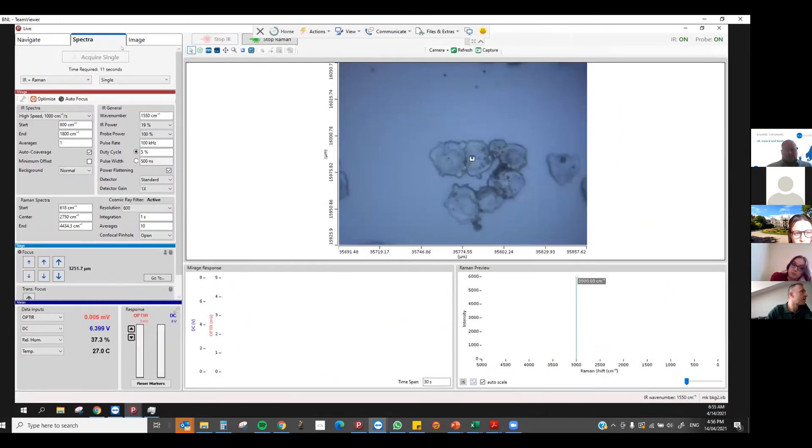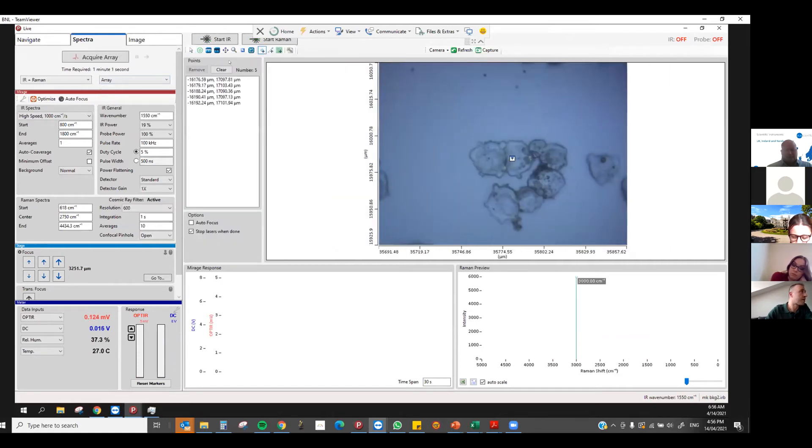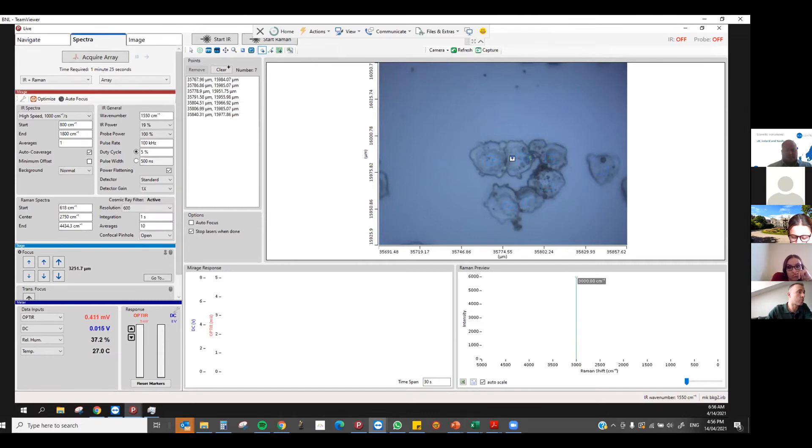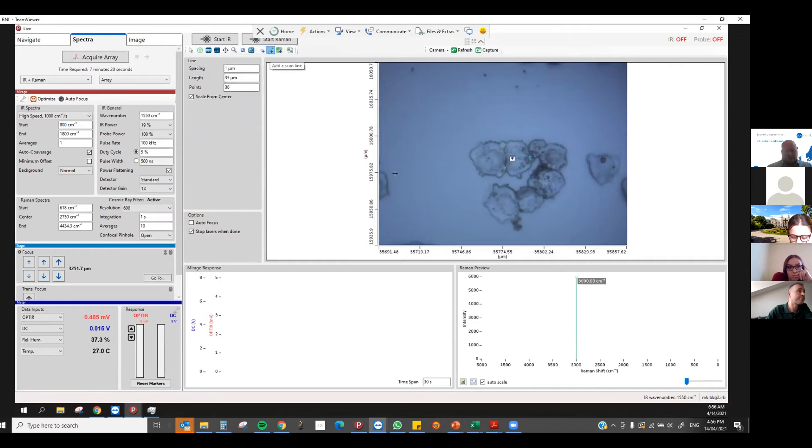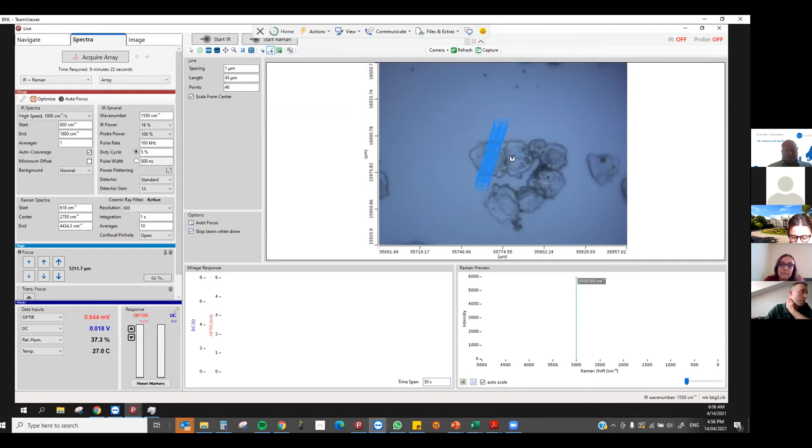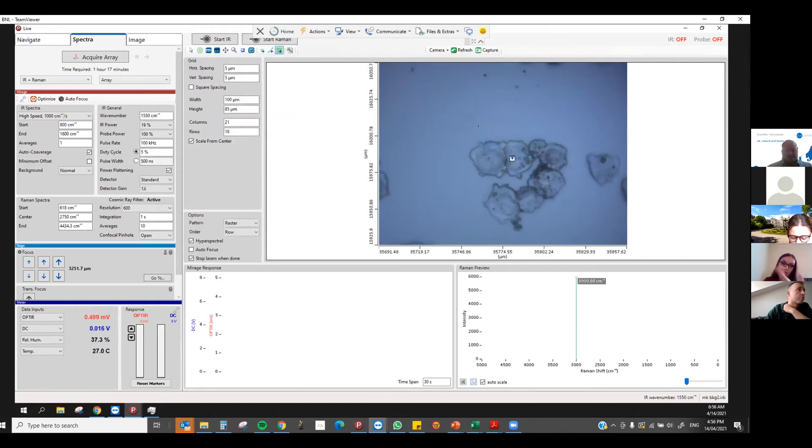Let me just stop the laser. We can do arrays. With the array button I can set up automatic collections. I can do multiple points. I can say here, here, here, here, and then I can go away for coffee and come back and it will automatically collect all of those. I can clear that. I can do a line array, which is going to be really useful as well. We can draw a line across and then we can specify the spacing. Spacing as little as about 100 nanometers works well. If you have a sample with some topology to it, you can do an auto focus. This is a fairly flat sample so we don't need to do that here. If you want to do a hyperspectral, you can put a box and then in a similar fashion you can specify the spacing.